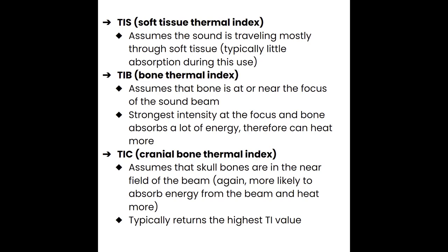TIB is when we are interacting sound with bony structures. And more often than not, you'll see the TIB being reported during fetal exams because we're very concerned that as those fetal bones harden and calcify, they're going to absorb more sound, making the fetal tissue more susceptible to heating. TIC then refers to cranial bone thermal index. This assumes that skull bones are in the very near field of the beam, which are more likely to absorb the energy from the beam and heat up more. As we saw in our image examples, the TIC during a transcranial Doppler had that TI value of 2.7, a very high thermal index.